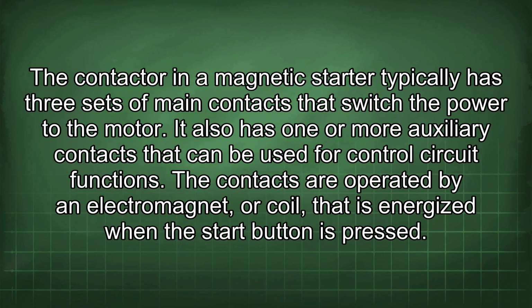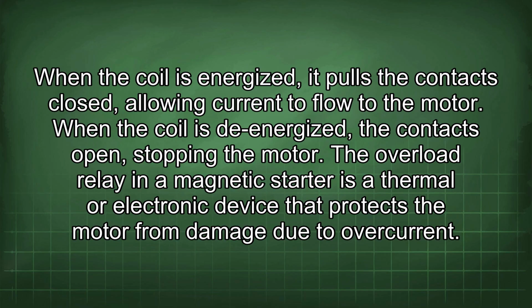The contactor in a magnetic starter typically has 3 sets of main contacts that switch the power to the motor. It also has 1 or more auxiliary contacts that can be used for control circuit functions. The contacts are operated by an electromagnet, or coil, that is energized when the start button is pressed. When the coil is energized, it pulls the contacts closed, allowing current to flow to the motor. When the coil is de-energized, the contacts open, stopping the motor.